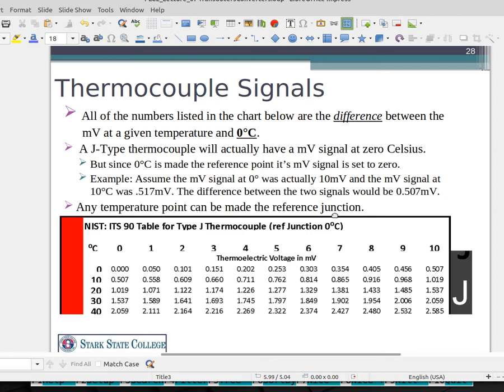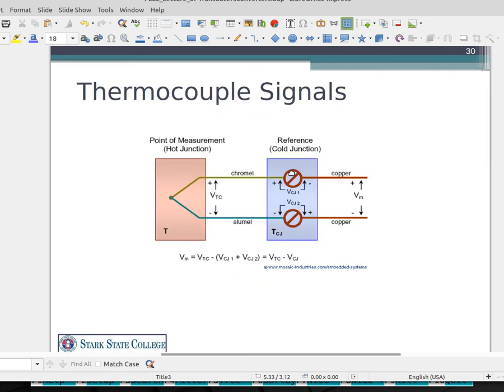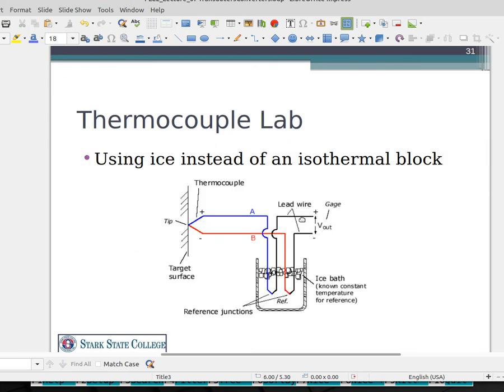We can buy specific cards for our PLCs to wire the thermocouple directly, or buy controller devices. You basically tell them you have a J-type thermocouple, wire it up, and the device has an electronic ice bath equivalent and the lookup table built in so it will know the temperature.